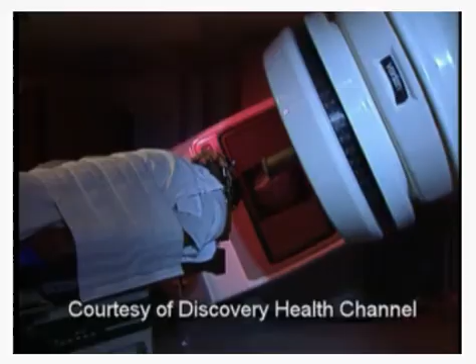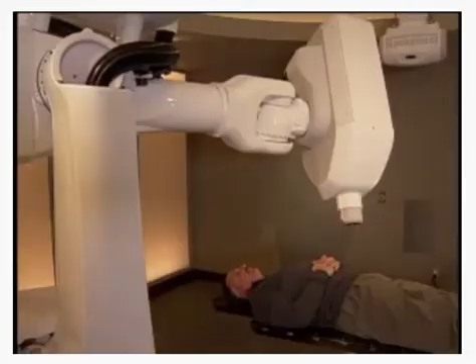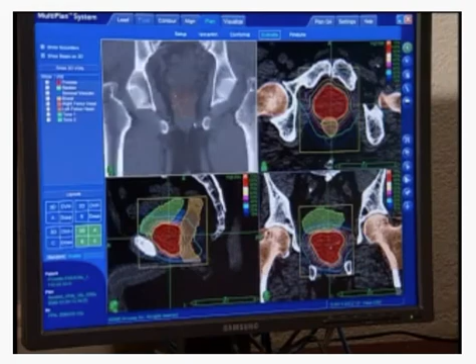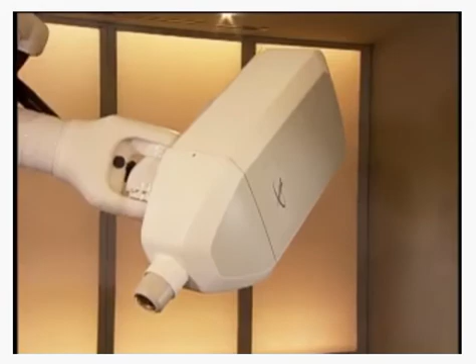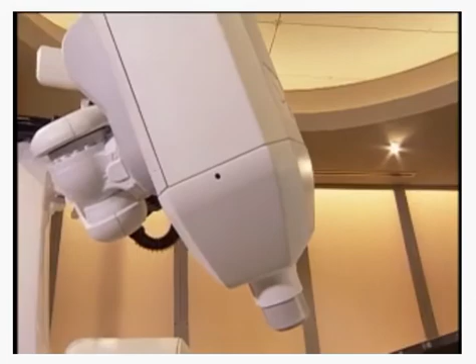Unhindered by the clockwise-counterclockwise constraints of conventional gantry systems, the CyberKnife system's robotic mobility has significantly improved dose sculpting capabilities and conformal dose distributions. Unlike the conventional radiation machines, the CyberKnife literally can dance around the room. Those radiation beams can come in from the head of the patient, the feet of the patient, the sides at multiple different angles. That's something our conventional radiation machines, which are fixed, are not capable of doing. And as a result of that, we can get very high doses into the tumor and spare the normal tissue surrounding it.